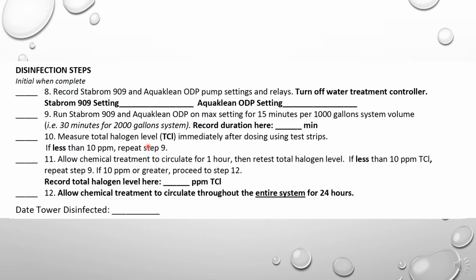You want to make sure that you are using the test strips so that you can actually measure if the total halogen level is at least 10 parts per million. Those Hach color wheels will not go that high, so it's important to make sure that you have a couple of these test strips from your associate director if you don't have any already on site when you are performing the startup procedure. If you get less than 10 parts per million, you're just going to repeat that max setting for 15 minutes per 1,000 gallons and remeasure.